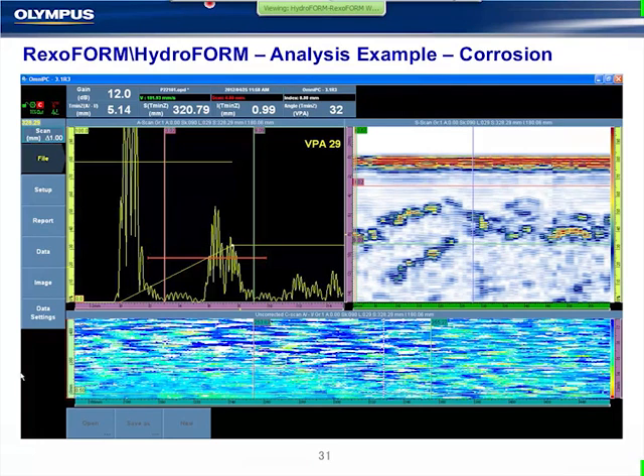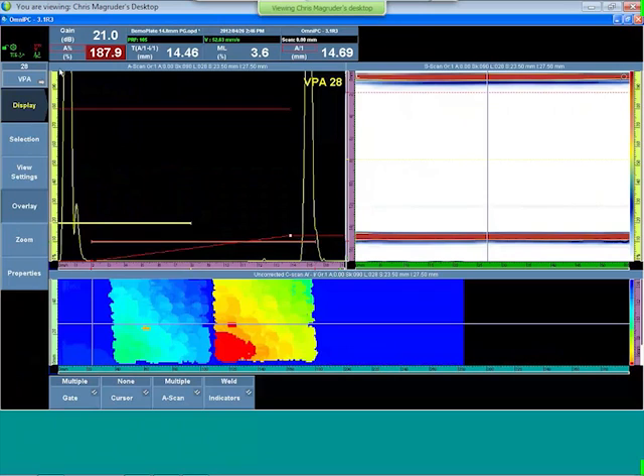Now available, just recently released, is the OmniPC offline analysis software for the OmniScan. So this is the same user interface as the MX2. It allows all of your previous data files from earlier generations of OmniScans or the latest MX2 to be analyzed offline. You basically have all of the functionality in the software that you would have on the instrument on a data file in pause mode.